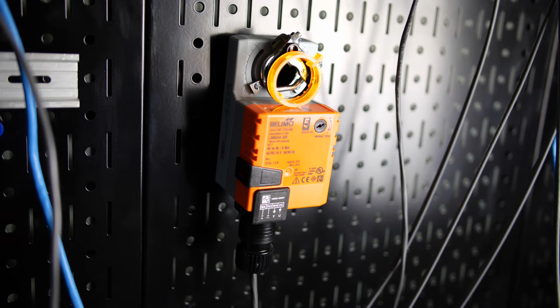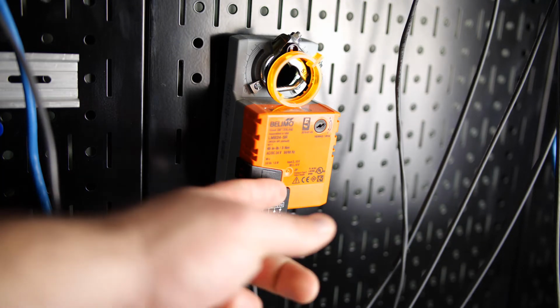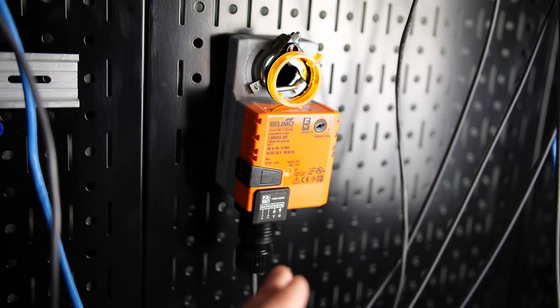But at the end of the day, there's really only 4 types of outputs that you're mainly going to deal with. Yes, there's pulse outputs. Yes, there's incremental or floating outputs. But the majority of the ones you're going to deal with are internally sourced, externally sourced voltage and current outputs. The thing with voltage or current outputs is we need to understand, are we using the same common? Now, I know we talked about shared commons, and I'm going to talk about this a little bit because we have about 3 minutes left in the video.